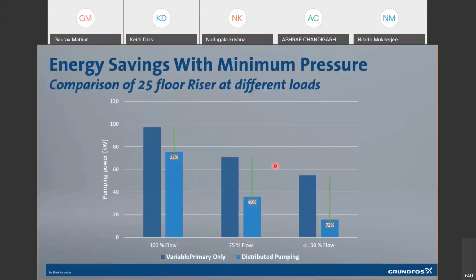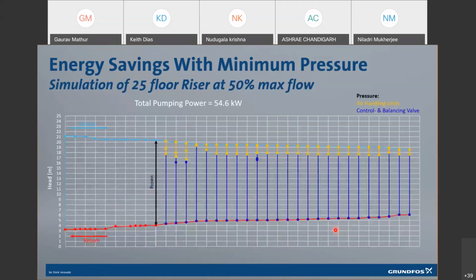Now, if we just look at one of the examples and do a comparison vis-a-vis a variable primary only system, what are the kind of savings which are possible? As you have seen in the system curve diagram, I have translated that system curve and put it in the form of a bar chart. And that tells you that as the load reduces, you are able to achieve much higher efficiencies. For this particular project, we were able to achieve 22% savings at 100% load. At 75%, we had 49%. At 50%, we have 70% saving possible. But this is a particular project. It may vary from project to project, but it will be in this kind of pattern only.